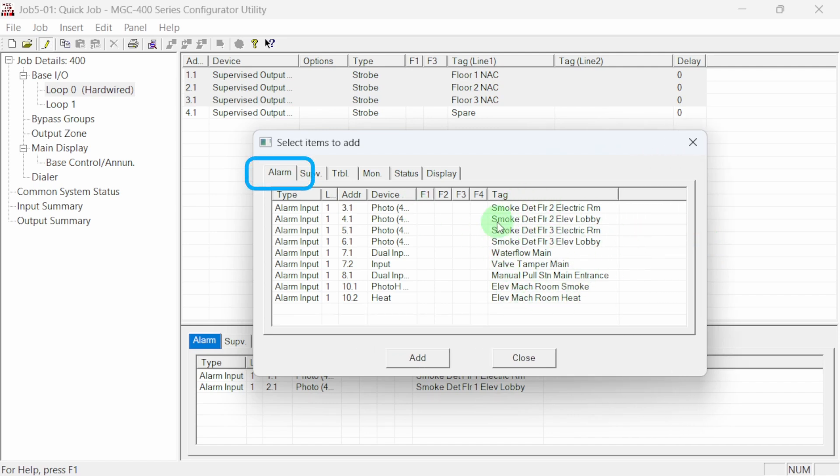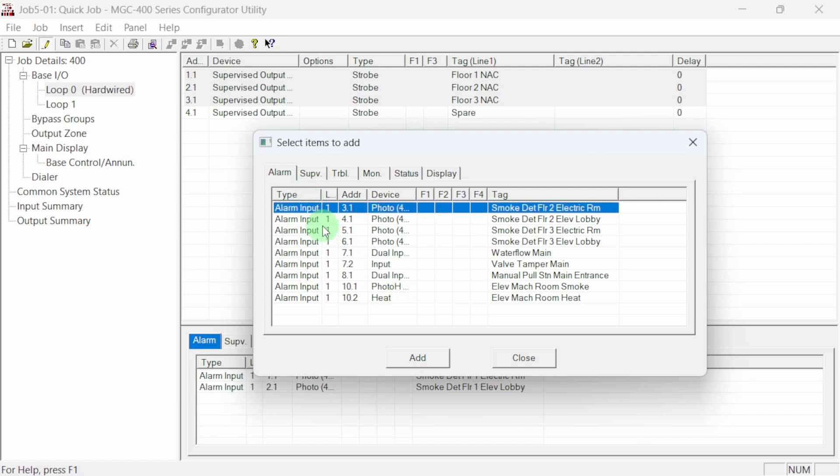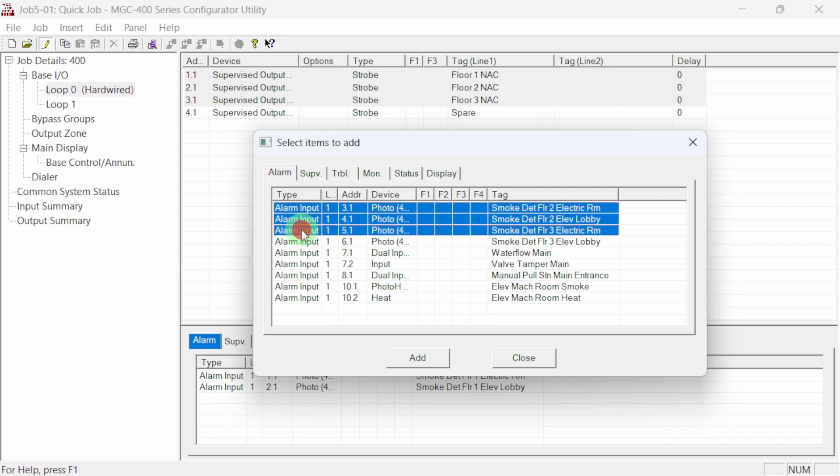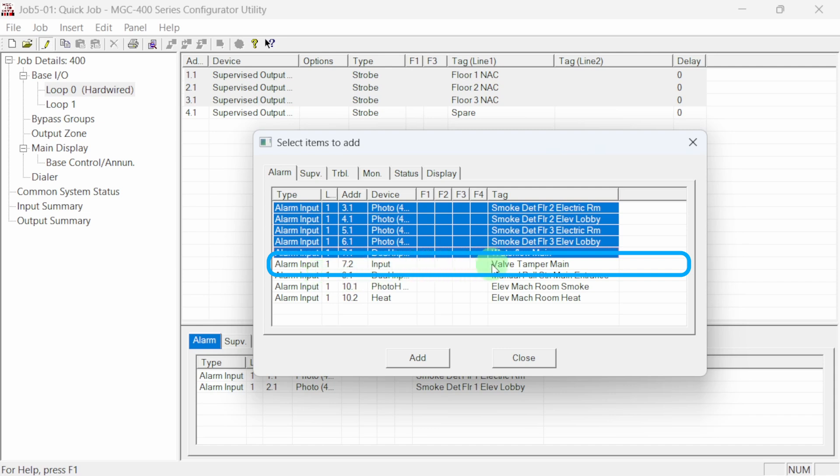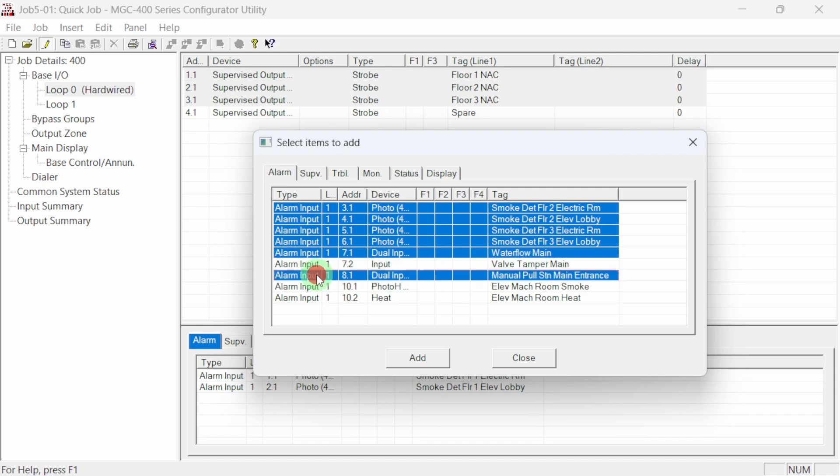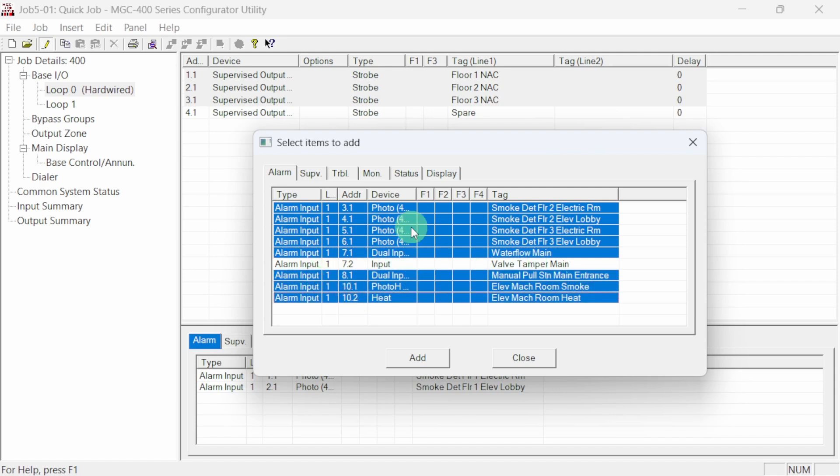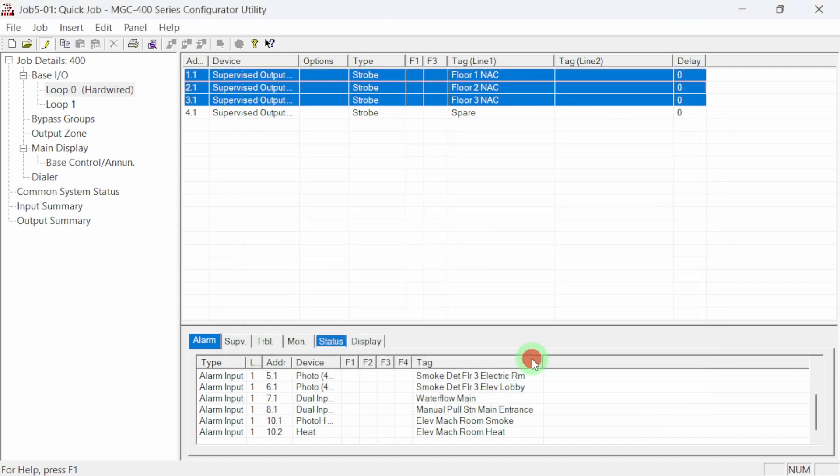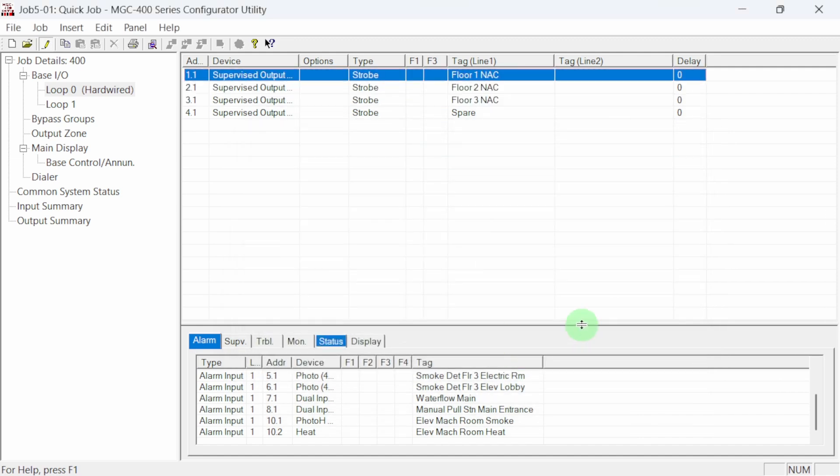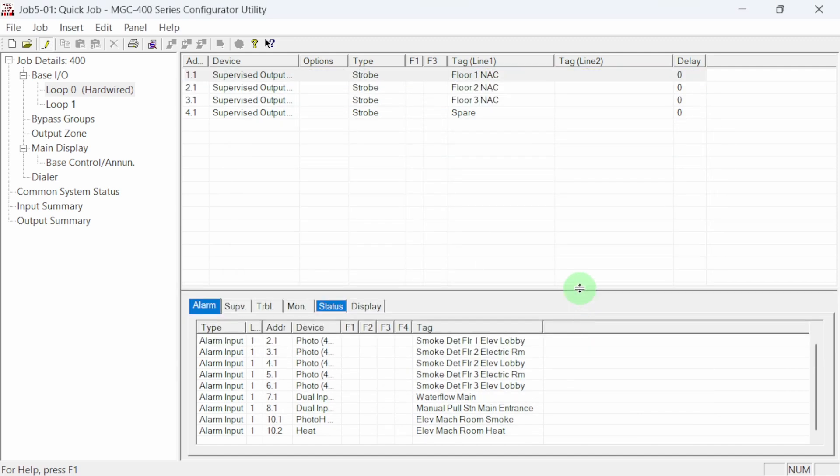all of the available alarm input devices are shown. Holding down the control key, we can select each of the alarm input devices that will activate the three selected NAC circuits. Here we notice that the valve tamper switch is in this alarm input list. We don't want this device to activate our NACs. It should be a supervisory type. We'll have to make that change. Continuing with the rest of the inputs, we select add. All of the alarm input devices are now correlated to all of the NAC circuits in one step.